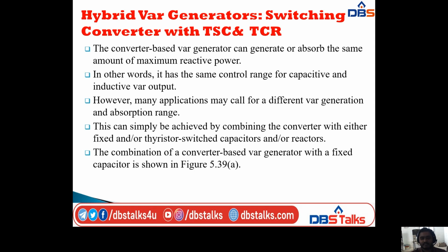In those, we are taking GTO thyristors, but here a hybrid generator means a switching converter with TSC and TCR, that is, thyristor switched capacitor and thyristor controlled reactor. Here the converter based VAR generator can generate or absorb the same amount of maximum reactive power. In other words, it has the same control range for capacitive and inductive VAR outputs.